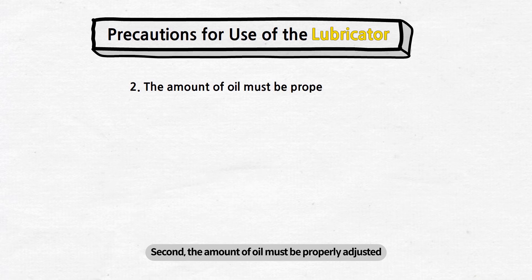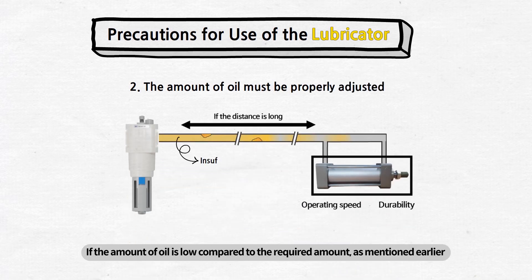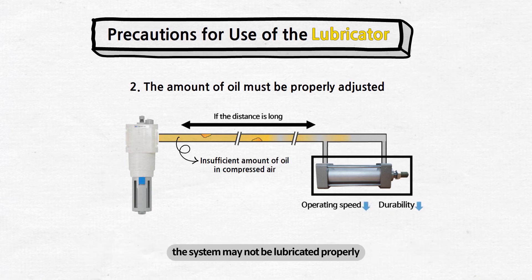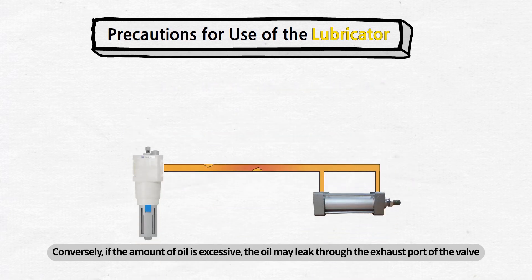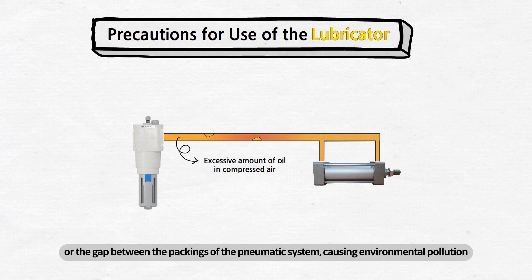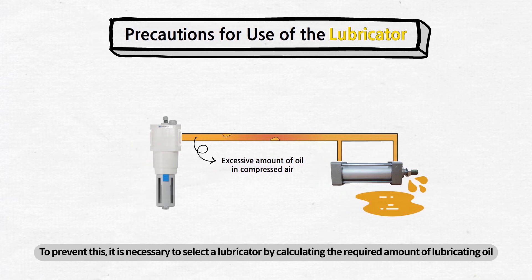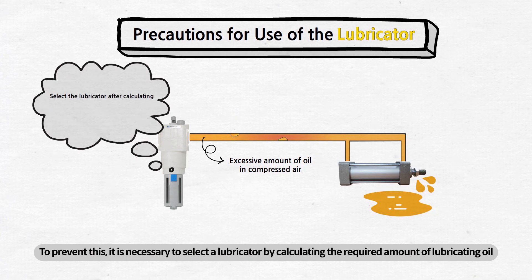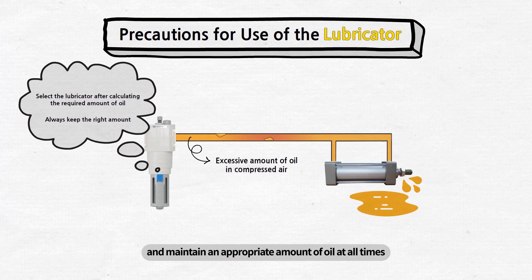Second, the amount of oil must be properly adjusted. If the amount of oil is low compared to the required amount, the system may not be lubricated properly. Conversely, if the amount of oil is excessive, the oil may leak through the exhaust port of the valve or the gap between the packings of the pneumatic system, causing environmental pollution. If the waste of oil continues, the cost loss could not be ignored. To prevent this, it is necessary to select a lubricator by calculating the required amount of lubricating oil and maintain an appropriate amount of oil at all times.